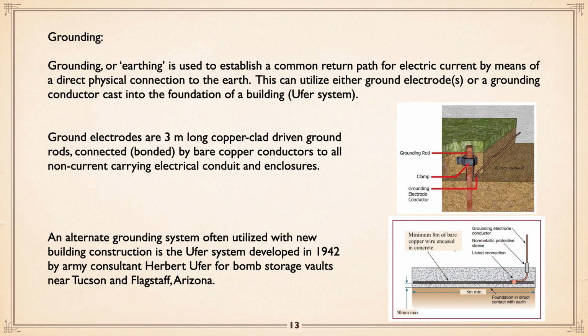Now, grounding. What is grounding? Grounding, or earthing as they call it here, is used to establish a common return path for electrical current by means of a direct physical connection to the earth. Yes, the earth can be a conductor. This can utilize either ground electrodes or a grounding conductor cast into the foundation of a building, a UFER system. Ground electrodes are typically 3 meters long, call it 10 feet, copper clad, driven into the ground, and bonded by bare copper wires to all non-current-carrying electrical conduits and enclosures. We talked about a kiosk enclosure. It would be grounded, or bonded is the expression.